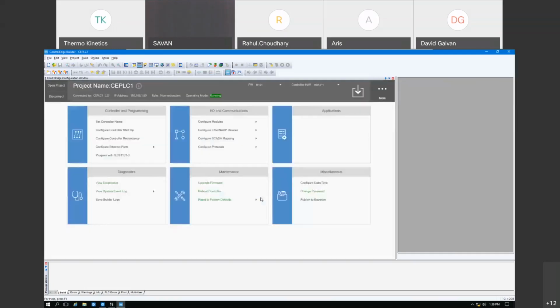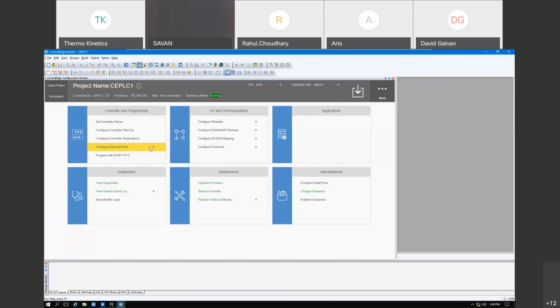Here's what I want to do when it starts up. Do you want to just go to running? You want to stop, last operating mode, or last operating mode running? I just leave it at last operating mode or stopped. That's my configuration for this. If I had to configure redundancy, here's where I would do that. Right now it's disabled. I do not have a redundant partner, but I would enable that if I were to add another CPM.